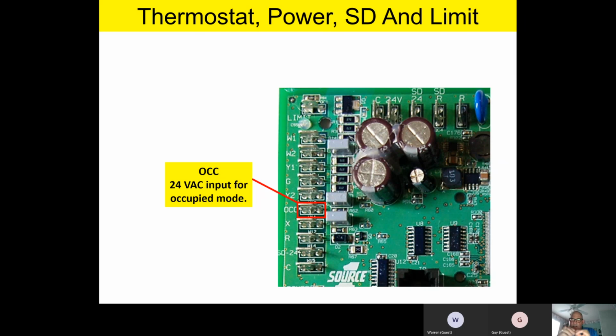So other than that, to your good question, I know I'm kind of expanding it and getting a little long-winded, but double check your low voltage. That's absolutely critical. With that unit just sitting there, you should read more like 26 to 28 volts with nothing on. But with everything running, with the low voltage going, the thermostat going, and if it's a heat pump, the reversing valve energized and cooling and all that, you should never drop below 24 to 25 volts with everything running.